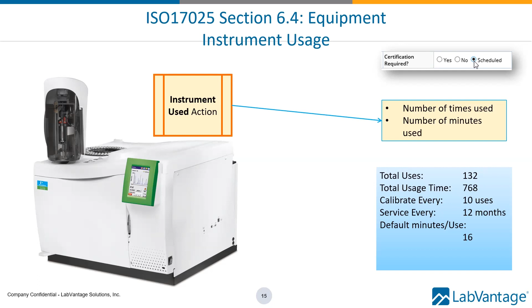In this slide, we see how that might look in your software. I can see here that we've decided to track the usage and to set some parameters around that. We also see at the bottom a certification schedule that's been set up to check the 1, the 10, and the 100 gram weights, and to do it every 8 hours and so forth. This is just one example of how you could set a plan around each piece of equipment or instrument for its routine checks as well as calibration and maintenance.